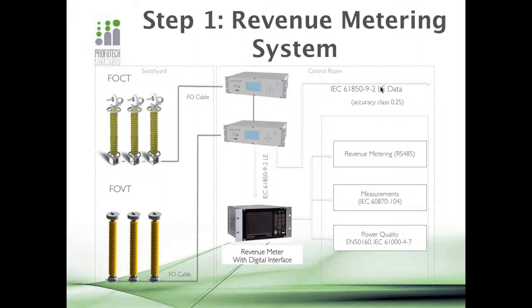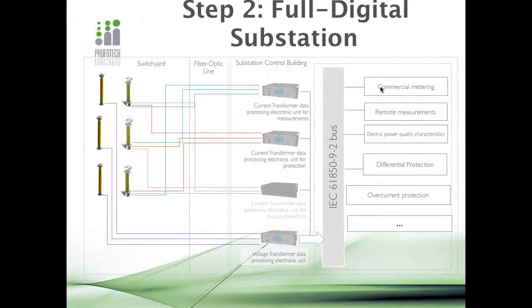So then, speaking about the revenue metering system that is proposed to be organized as the first step, we can make it already. We have special revenue meters with digital interface. They're actually produced also in Russia, but normally there are several revenue meter manufacturers who support IEC 61850-9-2. And we can integrate this into a smart metering system using some different protocols, and we can also establish the power quality, which is also possible with this fiber optic CT and VT.